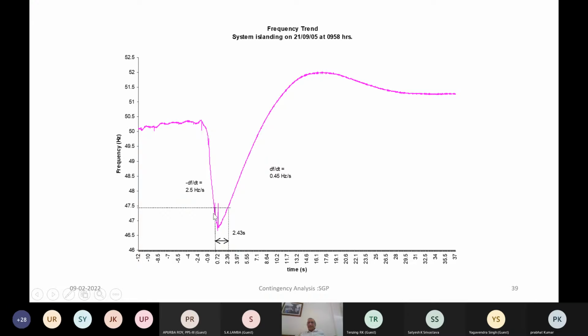You can see more in detail some of the events in here. This is a rate of change of frequency. You can see here it is 2.5 hertz per second. Frequency is collapsing. This graph remains below the 47.5 level for almost 2.4 seconds. So it is necessary that no generating unit should trip, though the frequency is below 47.5.